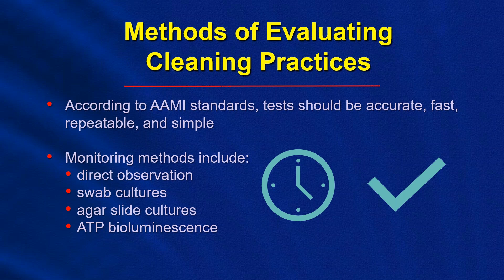So visual inspection can help when gross contamination is visible, but it's not a reliable method in measuring any level of cleanliness. Visual inspection cannot detect biofilm or unseen bioburden. Additional verification is necessary to ensure optimum patient safety, and there are multiple verification methods that can be used as an adjunct to assess cleaning efficiency.